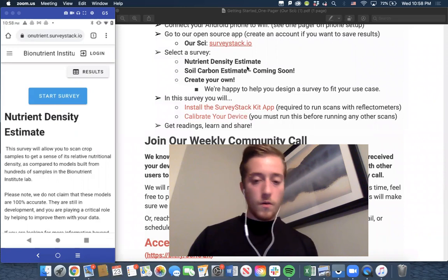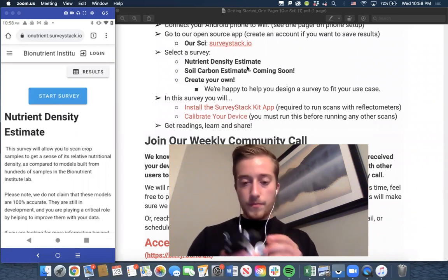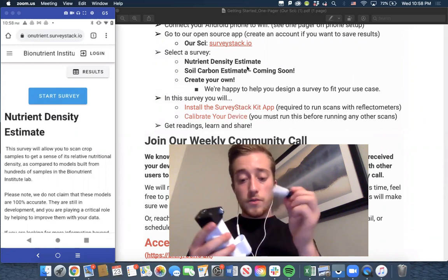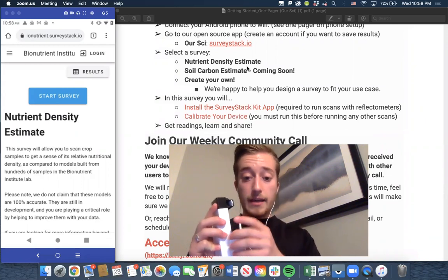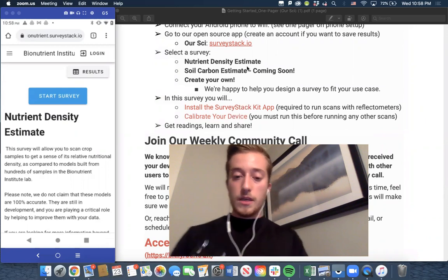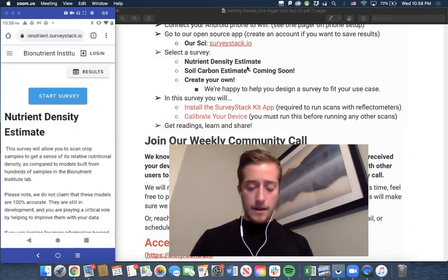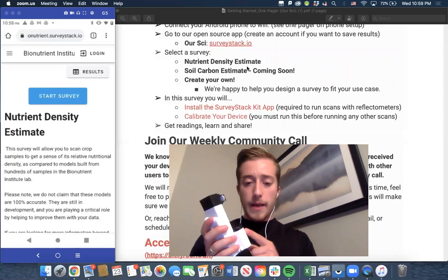So in the last video, we finished our calibration, right? And just as a note, one thing I forgot to list, once you calibrate, make sure you screw this back in place. You don't want to lose this piece. As I said, it would require us re-intaking the device and calibrating to a new one. So screw it back in place.